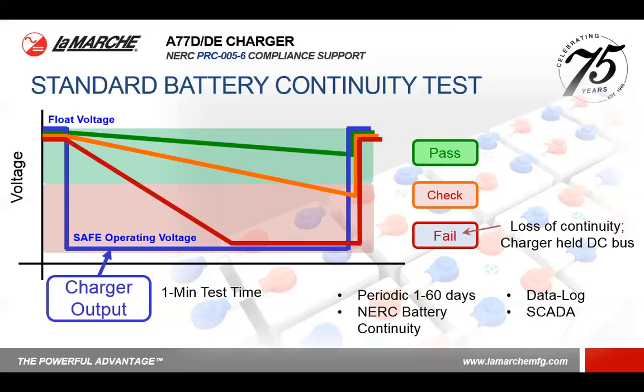So the battery test could be adjusted for a periodic test between once a day to once every 60 days. And all of this information is available over the internal data log or remotely over SCADA. And this does qualify for NERC battery continuity tests.